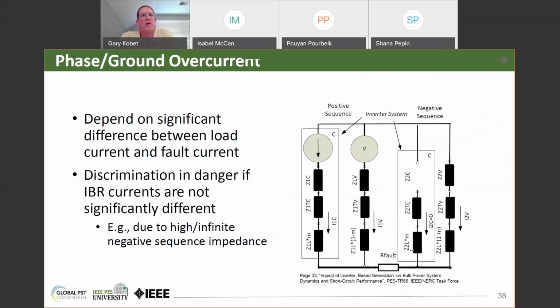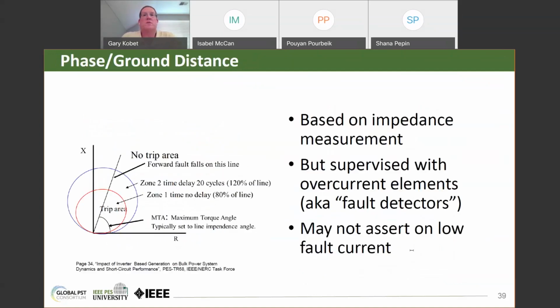I don't need to spend a whole lot of time on this. Some of this becomes redundant. For the phase and ground overcurrent elements, the issue again is if there's not significant negative sequence current for unbalanced faults, or there's not significant change between load current and fault current, then overcurrent elements may not be reliable. So in any case where you have overcurrent elements that are used for tripping, that's certainly a danger that the relay may not be able to discriminate between faults and load. Next slide, please. The same is true for distance elements that are supervised with overcurrent elements. Again, there has to be enough current for the relay to say, yes, there's a fault.